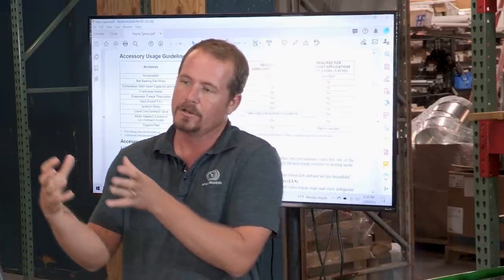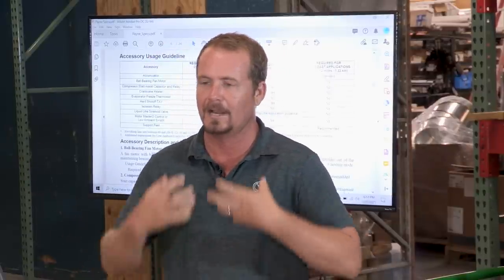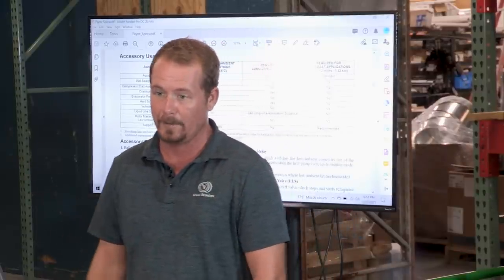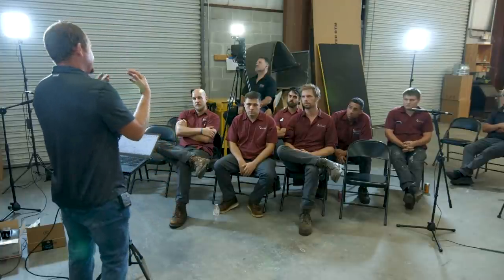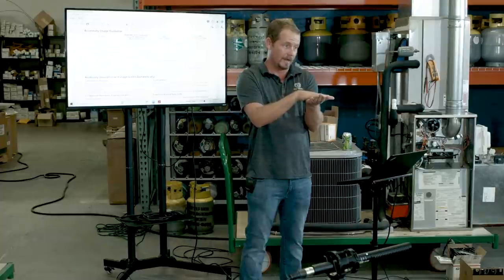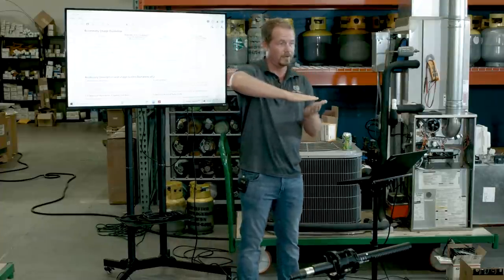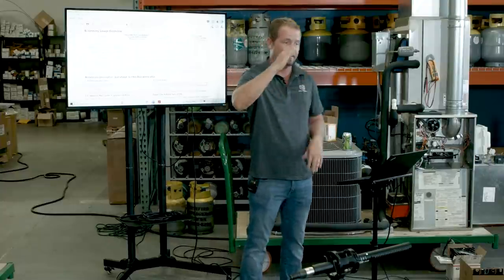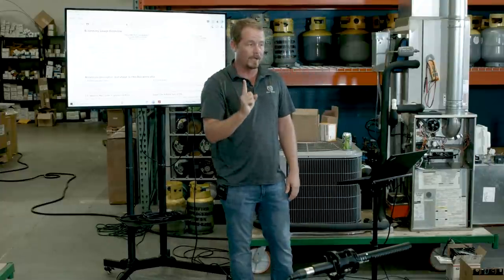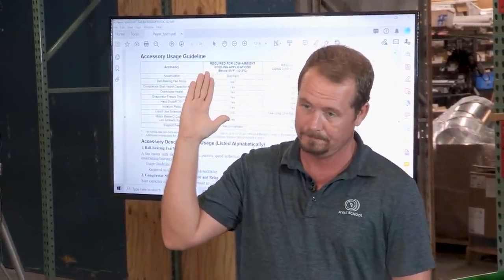And because your start winding isn't connected across the line, it's just dead ending into a capacitor, that stored additional potential is showing up. So it has to be set up so that initially those contacts in that potential relay are shut, so that the start capacitor actually does its job and starts, right? But then that difference in voltage between when it started and when the motor got up to full speed has to be enough to open those contacts. Otherwise, if those contacts don't open in that potential relay, what happens to the motor?